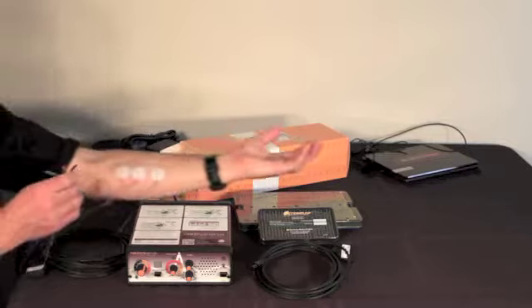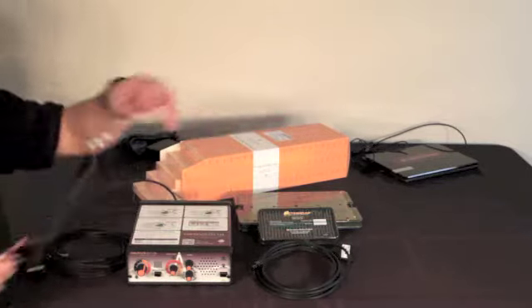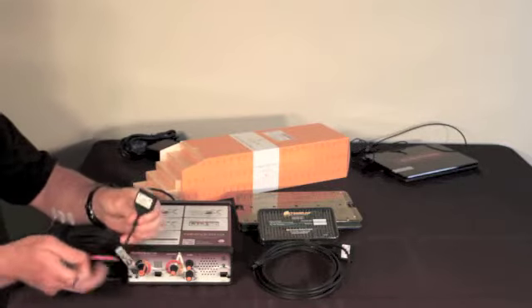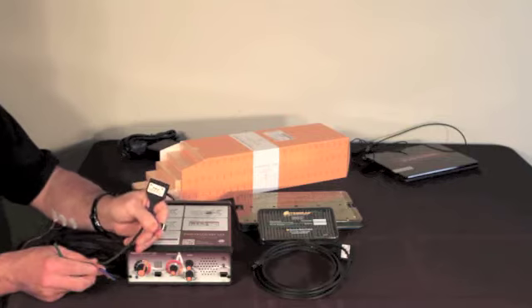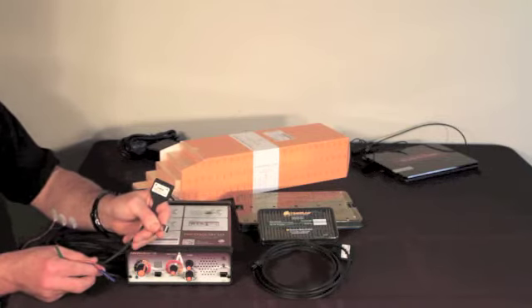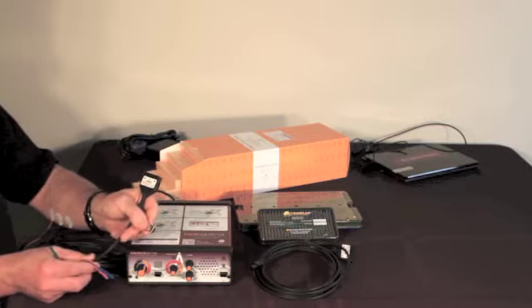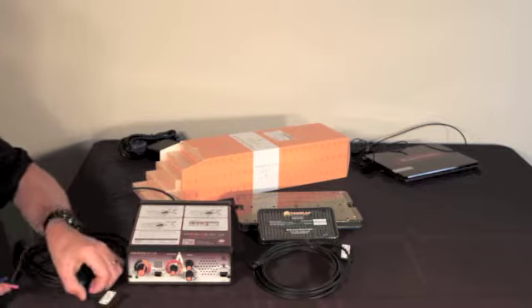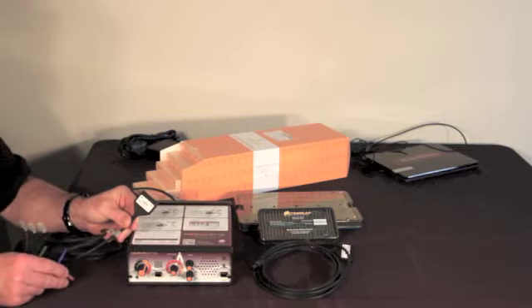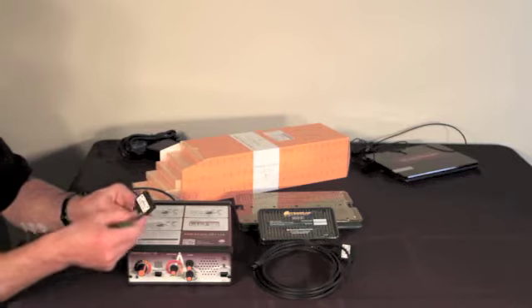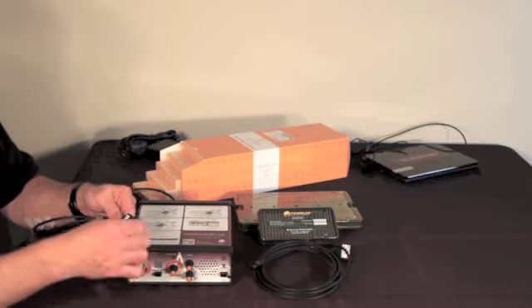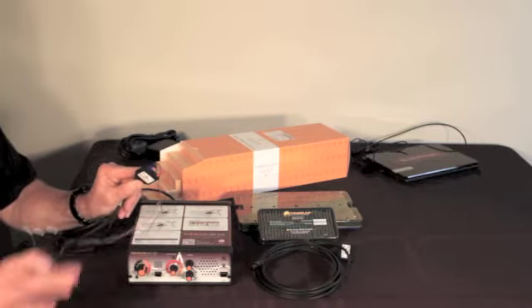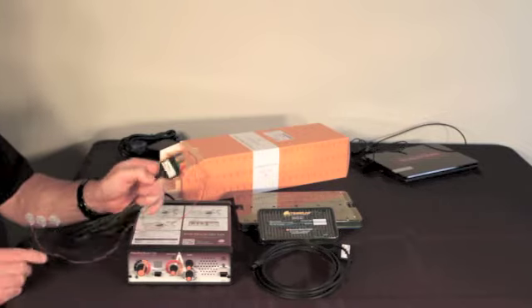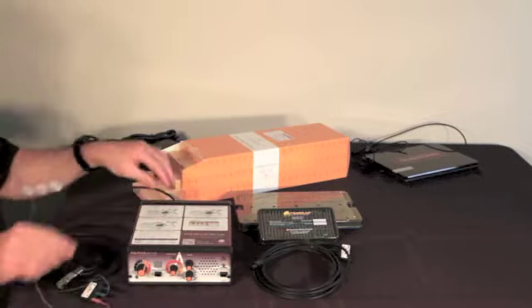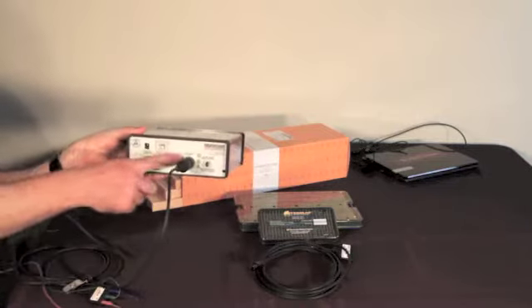Once you've properly prepped the skin surface and placed your hydrogels, then you head over to your EMG cable, which you use this clip to clip close to the patient's head, usually clipping it to the sheets or the pillow there near the head of the bed. And that's also shown in the illustrations on the top of the machine. So once you have this secured to the patient and the electrodes applied to the patient, you can then snap these into place, red, blue, and green in the middle, like so. At this point, make sure this EMG cable is connected to the back of the Nerveana machine at the port labeled EMG, and turn the machine on.